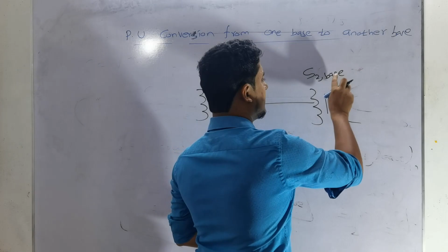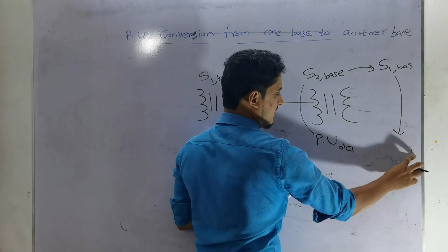For example, I am going to convert this base value to another base value, S1 base value. This transformer is defined with S2 base value, and now I am going to define the per unit with S1 base value. So the S2 base defined per unit is the old one, and the S1 base defined per unit is the new one. This old per unit is what's defined in the transformer nameplate; now we have to convert it to S1 base, which is called the new per unit.